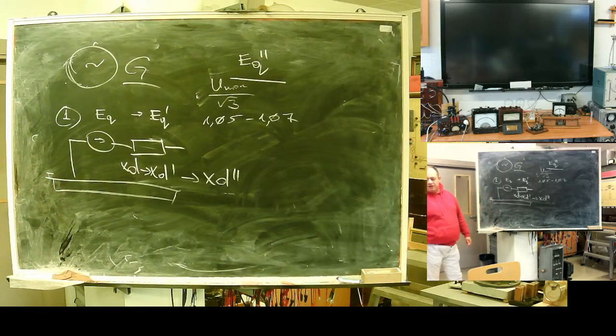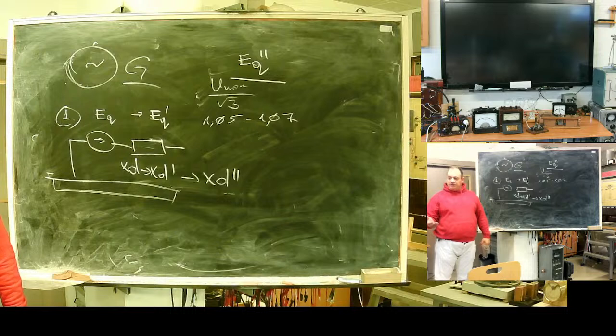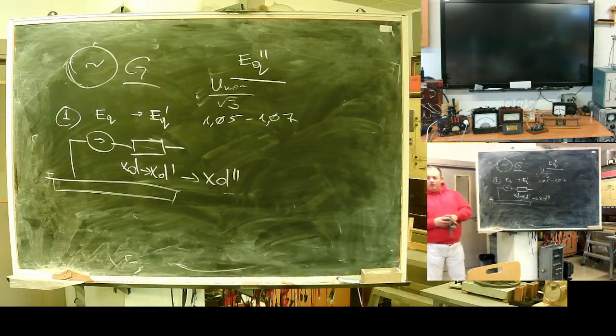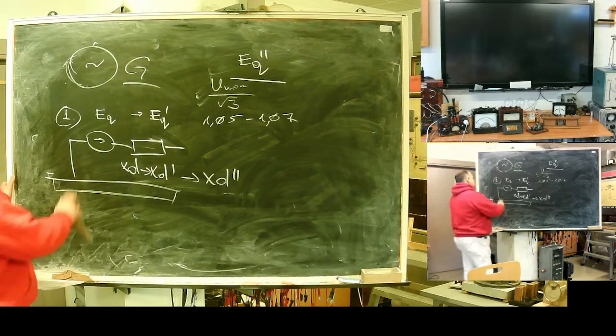Actually, if you like, the manufacturer of your generator will supply you with a reference sheet, and the reference sheet is good, but with the reference sheet also comes a testing sheet. Somewhere in the reference, or in this very nice thing, are commissioning. You will have a kind of commissioning protocol from when the machine was commissioned by the manufacturer. And in this commissioning chart, usually all data, all EMF and all resistance.